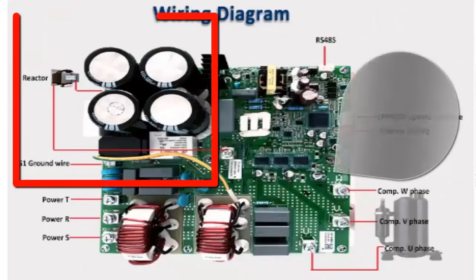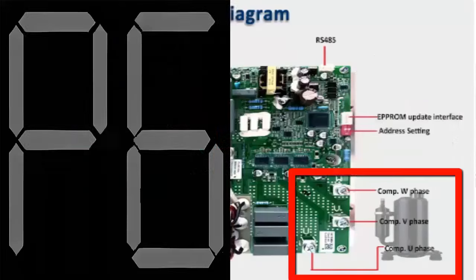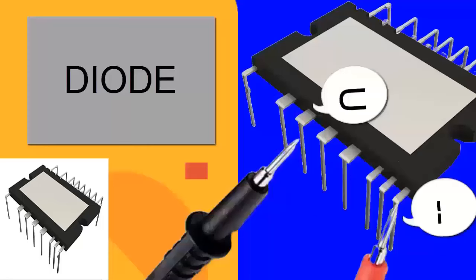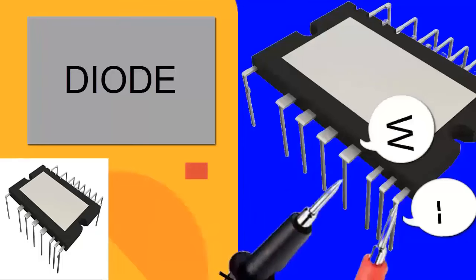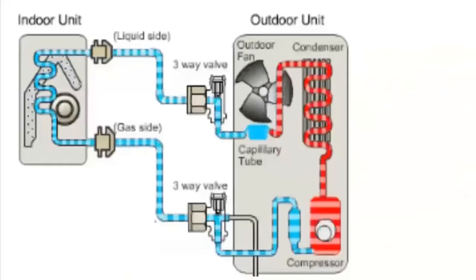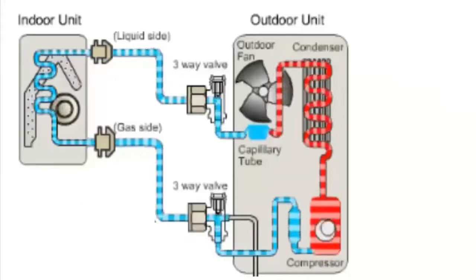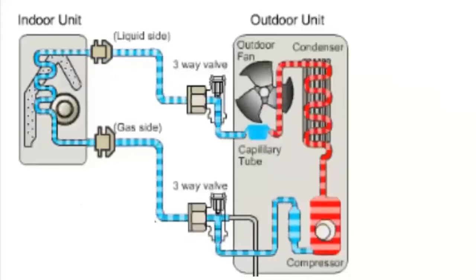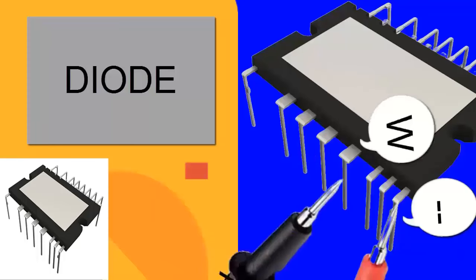3. If the problem isn't found in the compressor or the wiring, the next step is to check the condition of the intelligent power module, IPM. A. Ensure the unit is completely disconnected before proceeding. B. Set your multimeter to the diode test mode, and identify the model number of the IPM module to correctly recognize the terminals.